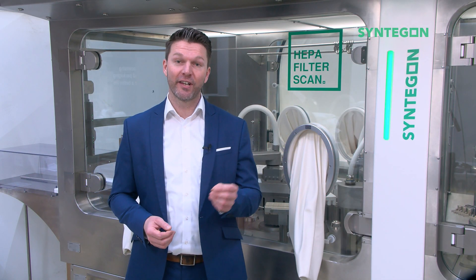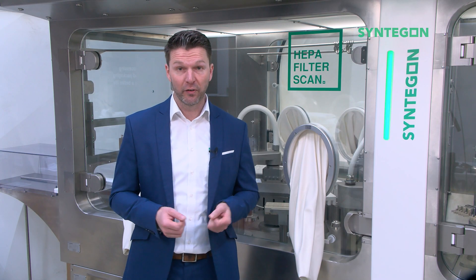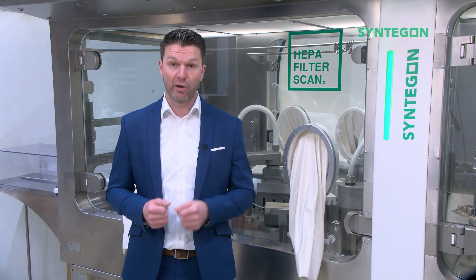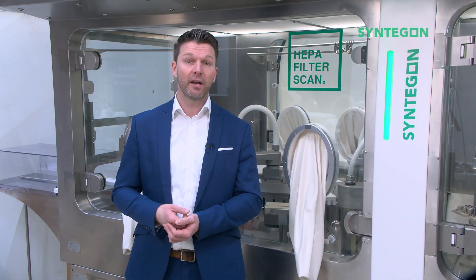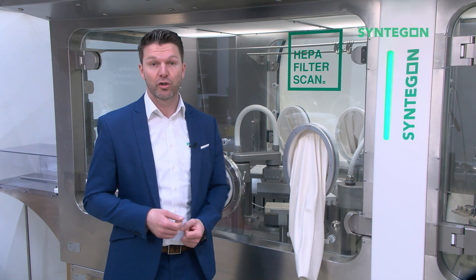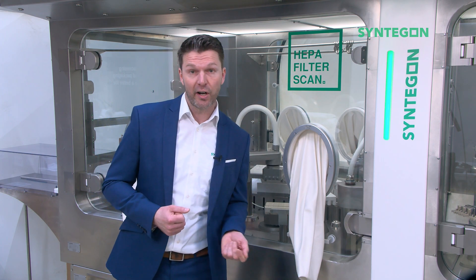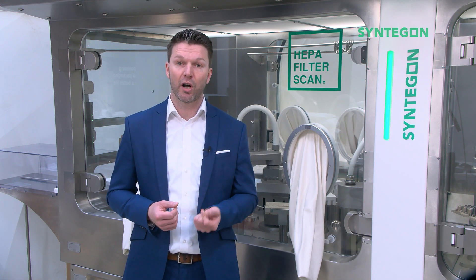Welcome to our glove integrity testing video series. Part one of the series is about changes in regulatory requirements coming along with the new Annex 1. Aseptic fill finish lines require appropriate technologies such as RABS or isolator systems. These systems are typically equipped with gloves to shield the product from operator-borne contamination, and on the other hand, to protect the operator from possibly hazardous products.